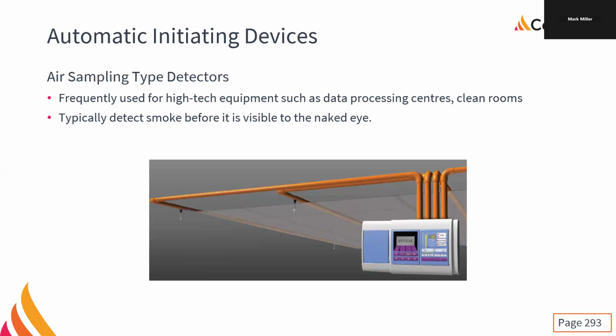And so when you run an elevator car from the bottom floor to the top floor, and if it runs non-stop, you're actually going to pressurize the air at the top because it's a piston, right? It's a leaky piston because there is airspace around the side, but it's still going to pressurize, and we can overpressure the air sampling detector, and we can cause troubles and faults on it. So it can be problematic in places like elevator shafts.